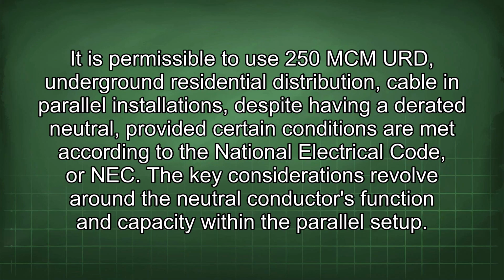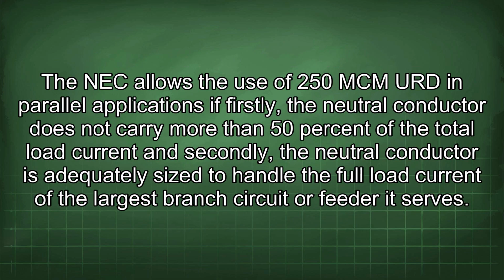It is permissible to use 250 MCM URD (underground residential distribution) cable in parallel installations despite having a derated neutral, provided certain conditions are met according to the National Electrical Code, or NEC. The key considerations revolve around the neutral conductor's function and capacity within the parallel setup. The NEC allows the use of 250 MCM URD in parallel applications if, firstly, the neutral conductor does not carry more than 50% of the total load current, and secondly, the neutral conductor is adequately sized to handle the full load current of the largest branch circuit or feeder it serves.